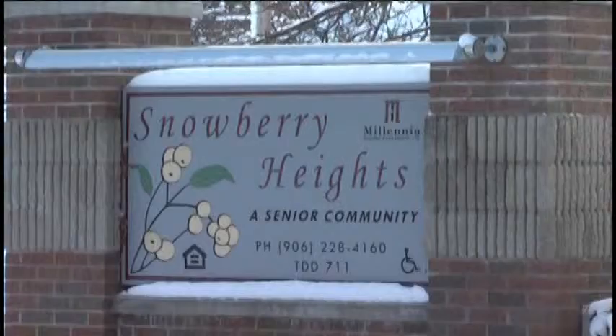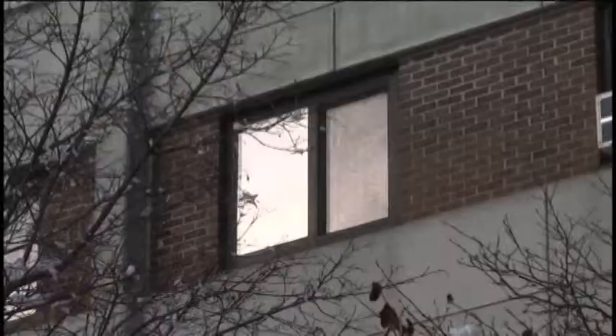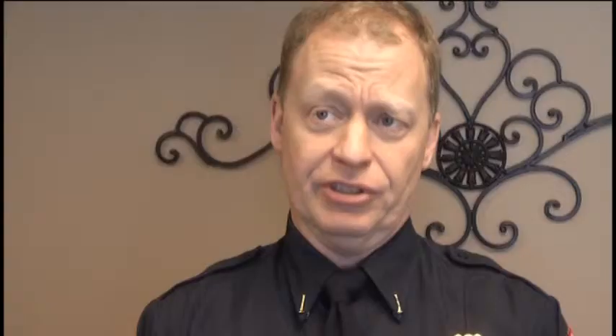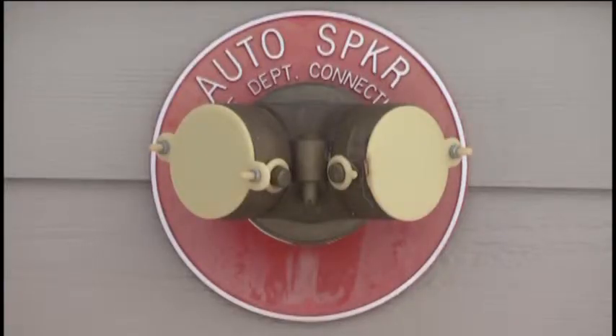At a similar building like Snowberry Heights in Marquette, Fire Lieutenant Jeff Green says the multiple stories could actually be a good thing. Because everything is so compartmentalized, that allows us to keep people in place while we deal with the issue. There are also a number of features put in place to slow the effects of the fire before firefighters can respond — eight-inch cement block walls, fire doors compartmentalizing the floors, a sprinkler system, fire alarm system, and smoke detectors. Fire doors are triggered to release when the alarm goes off, keeping smoke and fire under control and holding things to the seat of where the fire is, limiting the amount of spread. For the most part, it's safer and better for residents to defend in place, compartmentalize, and deal with the issue at hand.